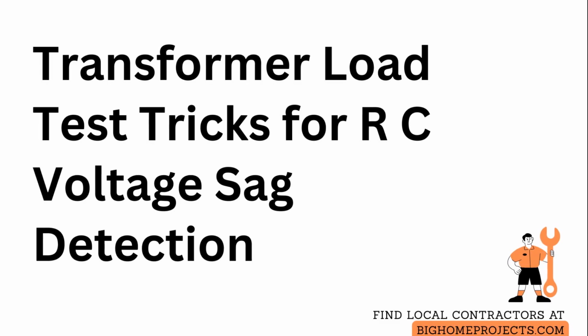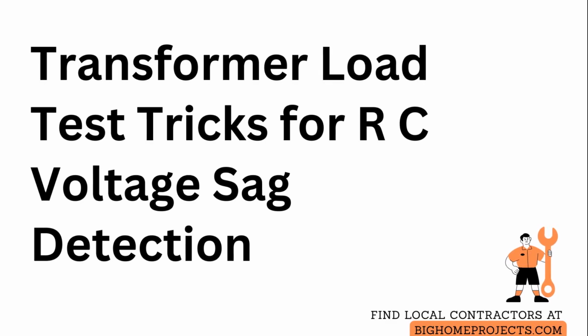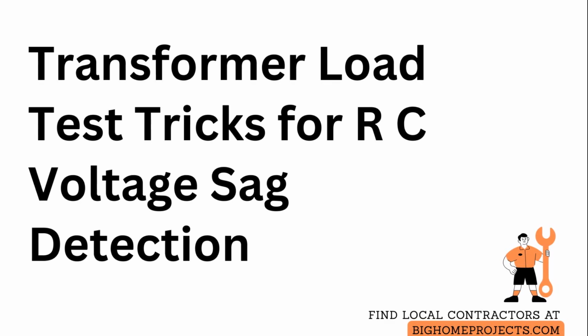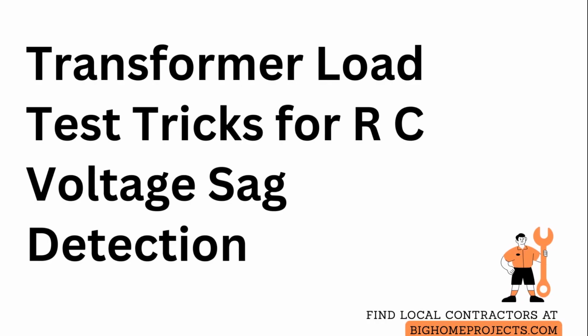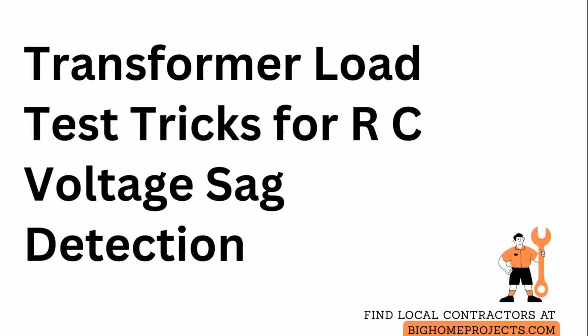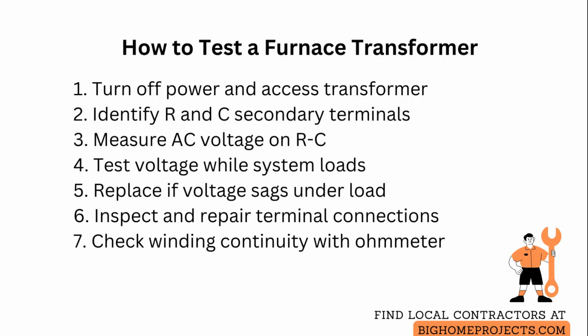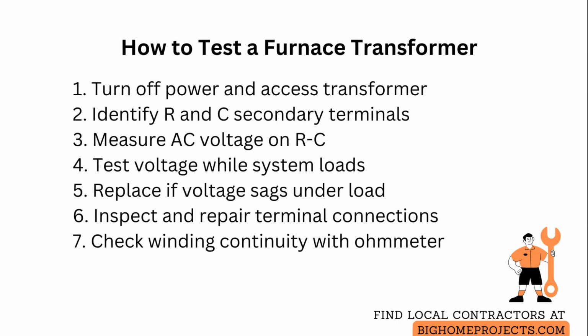Check the furnace transformer is supplying a stable secondary voltage between the R and C terminals under actual load to confirm it is not overloaded or faulty. Start by switching off power to the furnace at the service switch.